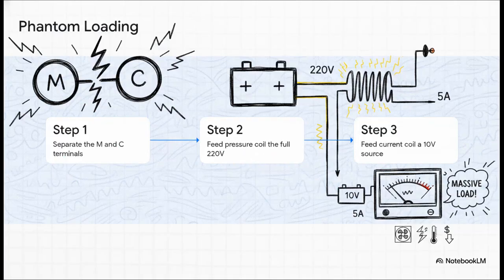So, how exactly does this phantom magic trick work? It's incredibly clever. First, you make sure those M and C terminals are completely separated. Next, you feed the pressure coil the full rated 220 volts. Finally, since the current coil has super low resistance, you just feed it with a tiny, isolated 10-volt source, just enough electrical push to drive the 5 amps of current you need. By driving that tiny separate voltage source through just the current coil, the watt meter is essentially tricked into thinking it's reading a massive load. You get a perfect calibration test, but you slash the energy waste and keep everything nice and cool.